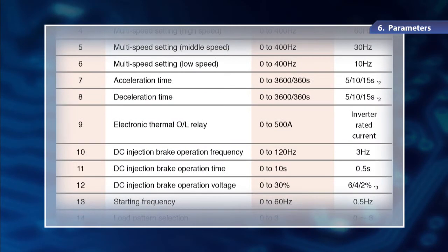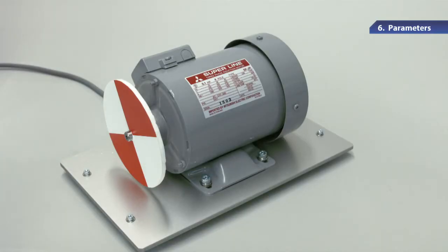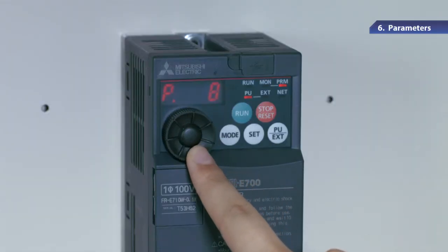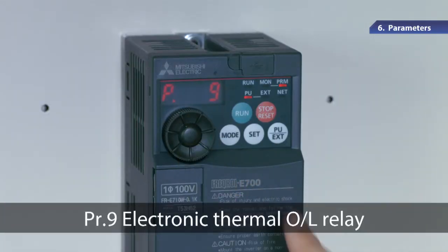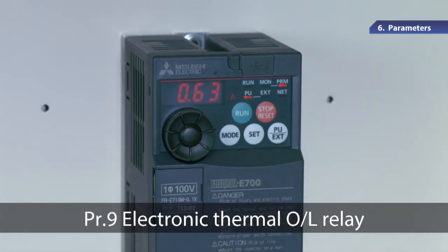First of all, let's set the Rated Motor Current value to protect the motor from overheating due to an overcurrent. The Rated Current value is the specification set to run the motor and is specified on the motor nameplate. To set the value, use parameter number 9, which is for electronic thermal OL relay.